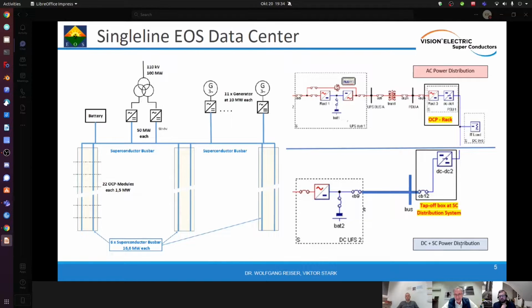And this is the miraculous thing about superconductors. Superconductor is really a nice material, and you can conduct currents without any losses, and therefore you can operate at a very low voltage level. Here, the voltage level on the lower scheme is the voltage level of your battery—it could be 400 volts, 500, 600 volts, or whatever you like as a battery voltage. This voltage can then be conducted directly, close to your racks, and that gives a lot of advantages.